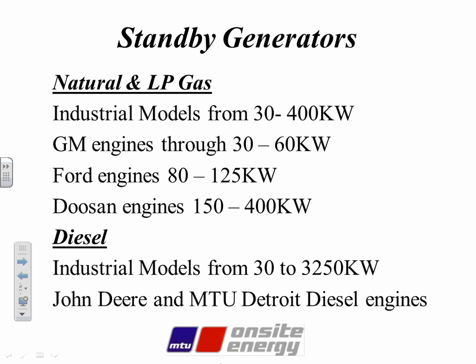On the natural gas side, LP gas, we have industrial models from 30 to 400 kilowatts. And this is standby stuff now. The GM engines are on 30 to 60 kilowatts. Ford engines on 80 to 125 kilowatts. And we use a Doosan engine from 150 to 400 kilowatts. On the diesel side, we have industrial models from 30 kilowatts to 3,250. On the small end, up to about 200 kilowatts, we have John Deere engines. And above that, we are exclusive MTU Detroit Diesel engines.